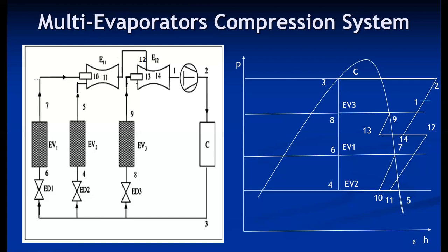This system is used in transport air conditioning systems. The main role of the ejectors is to assist the compressor by pre-compressing the refrigerant before it enters the compressor, reducing the compression ratio and saving compressor work. The ejectors simultaneously suck the refrigerant from their respective evaporators. Consequently, the COP is improved — approximately 10 to 15 percent compared to a normal compression system.